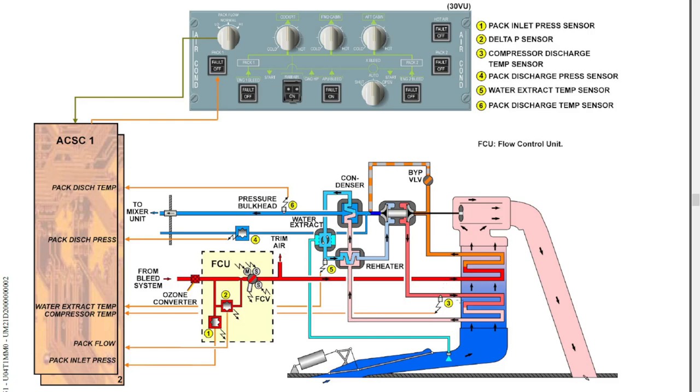Right, now we had two scenarios: up to 180 degrees, which is detected by the compressor discharge temperature sensor, the system operates in normal manner. From 180 to 220 degrees, now the computer starts to close the flow control valve in a modulated manner. So in case the temperature goes to 260 degrees and beyond, the computer will have to take an action. So what is that action? So now up to 180 degrees, normal operation, 220, airflow reduced using flow control valve.